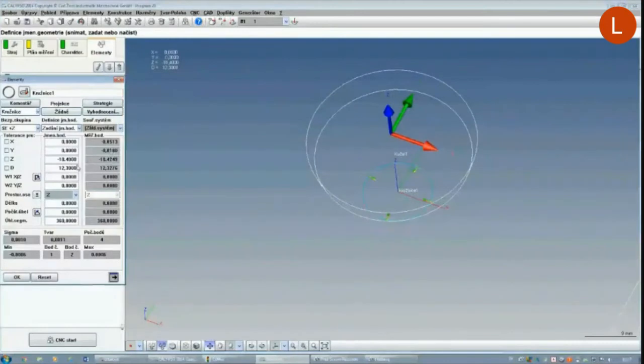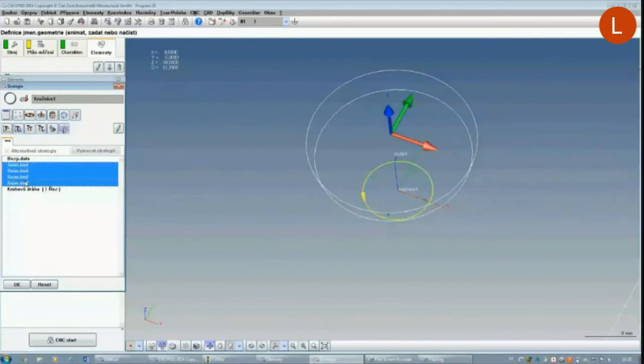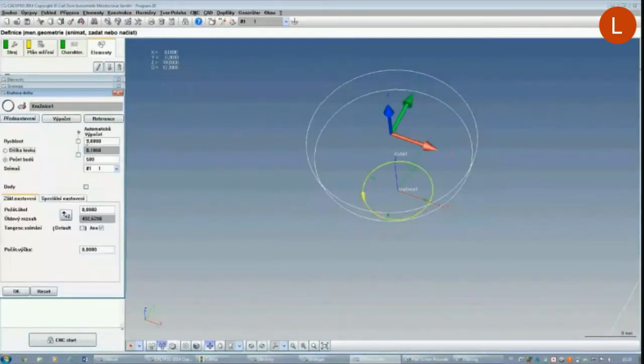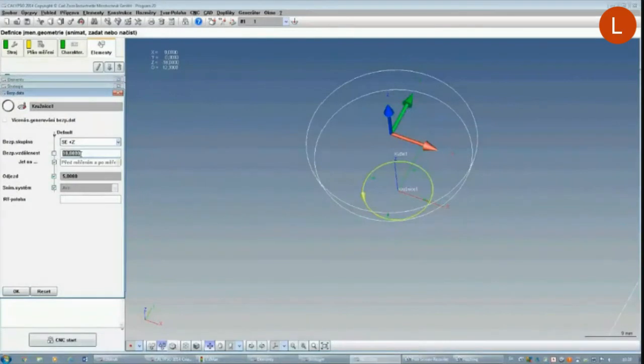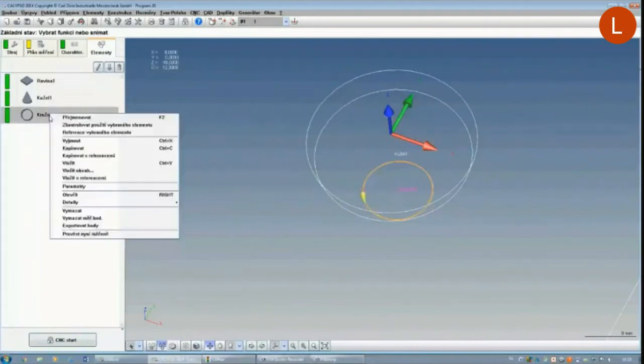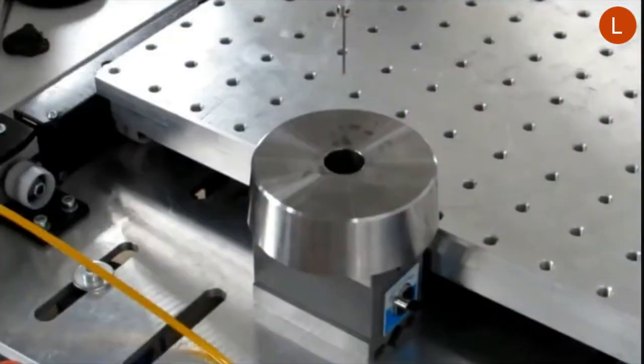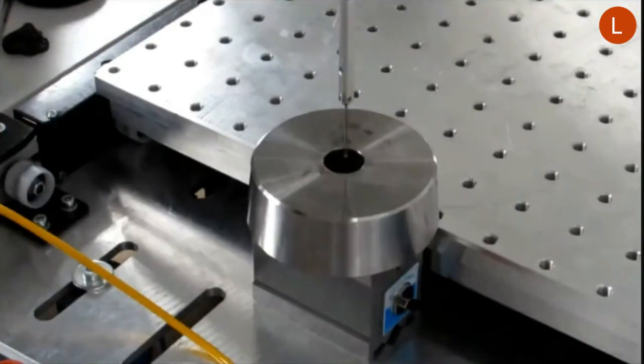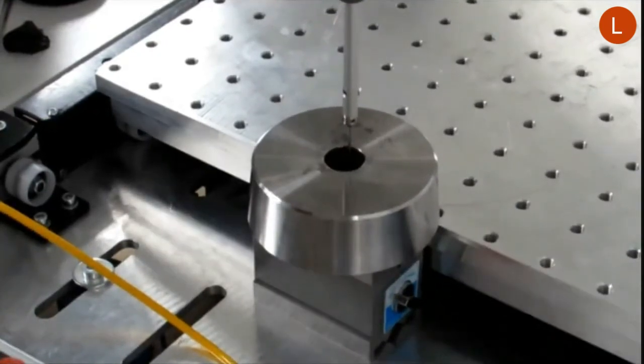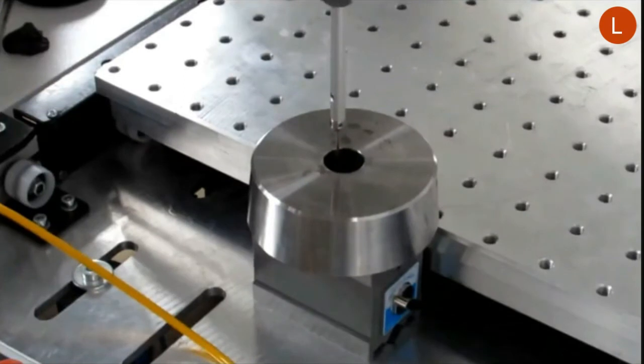After the part is aligned by an automatic process, it is possible to define the elements that are needed to evaluate certain characteristics. In this case, a circle with a diameter of 12 mm is measured and evaluated with one circular path. The scanning speed is set to 3 mm per second and the step length to 0.05 mm. Because it is a measurement of an inner hole with a relatively small diameter, the security data must also be set.